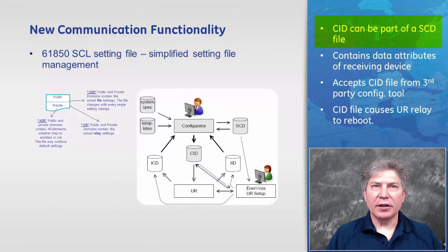The CID, the configured IED description file, describes the required settings of an IED and is intended for transmission of configuration from an IED configurator tool to the IED. The CID file can be part of a SCD file, which we'll talk about next.